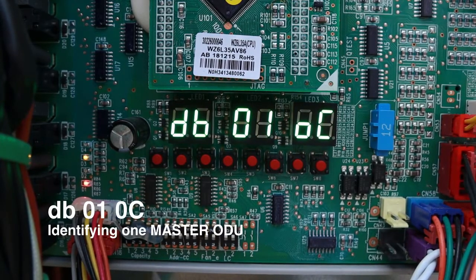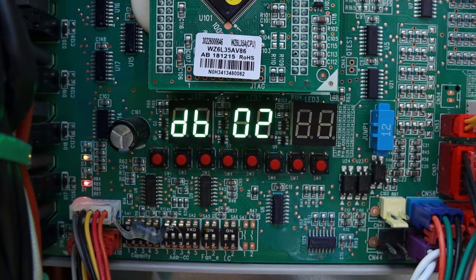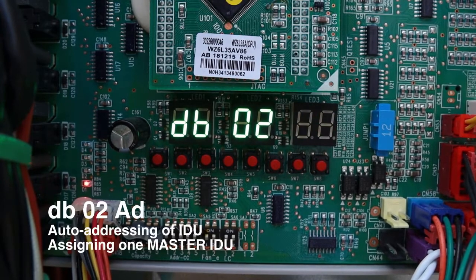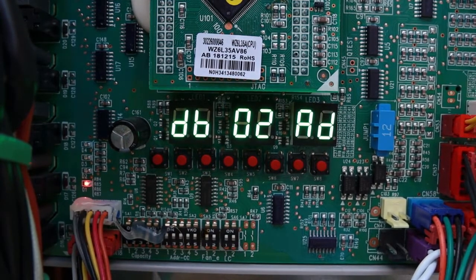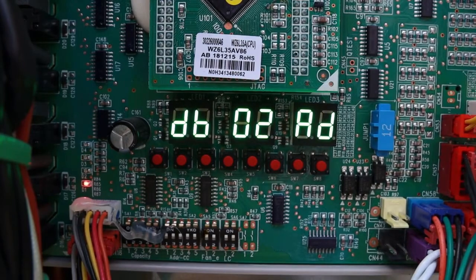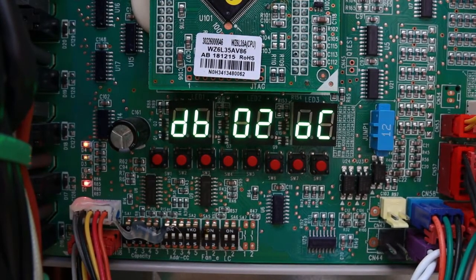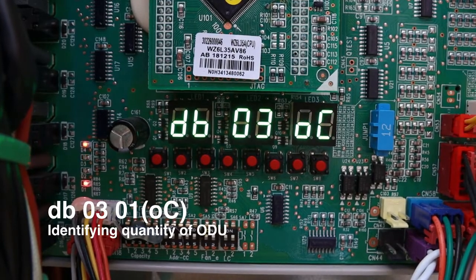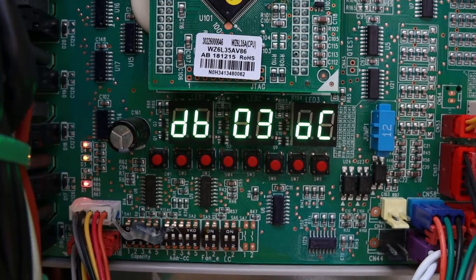Step 1 is checking for a master outdoor unit. Step 2 is auto-addressing IDs for the evaporators — it's automatic, takes about a minute, and assigns a master unit for operation of the whole system. Step 3 is identifying the quantity of condensing units; since there's just one in this case, it will automatically jump to the next step.